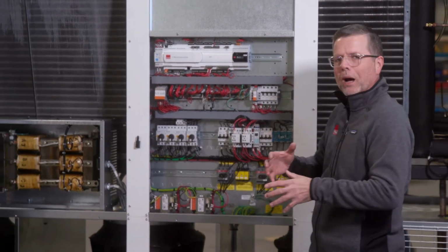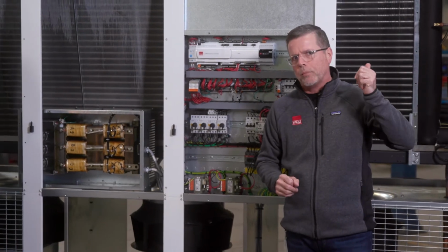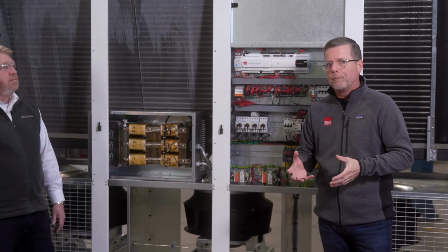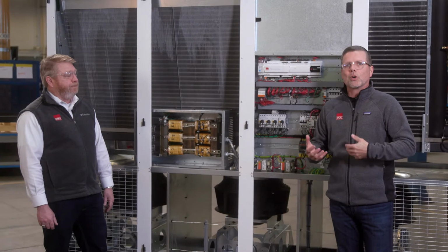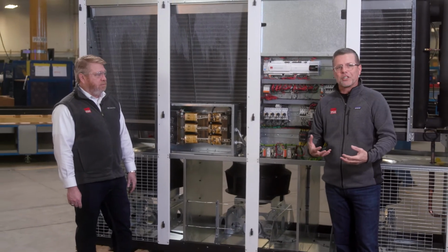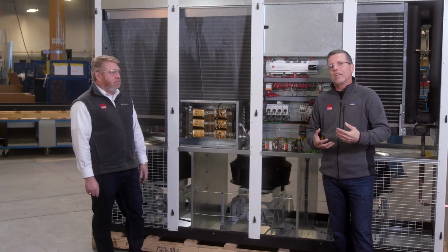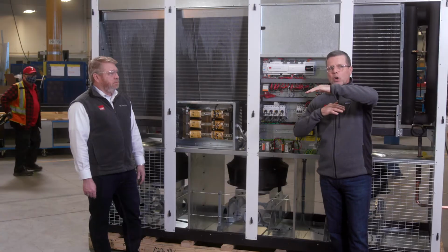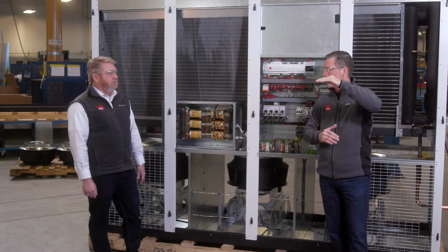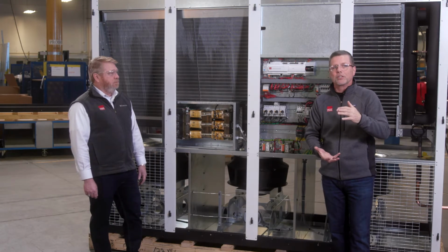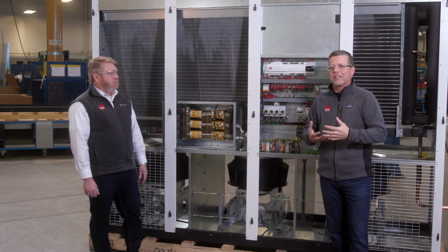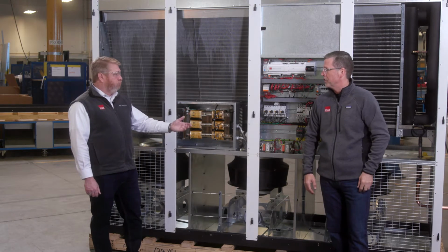One other thing that we'll probably try to capture with a different camera angle at some point on chilled water units as well, air bleeders are a big deal. So during the install, during the filling and commissioning of the chiller loop, we want to be able to give the installers and the service personnel the easiest possible way to bleed any air out of our systems. So maybe we'll try to catch another camera angle at some point. But basically, you'll see air bleeders on both our supply and our return headers in our chilled water units, and that's not a thing that needs to be configured. That's a standard option for us.